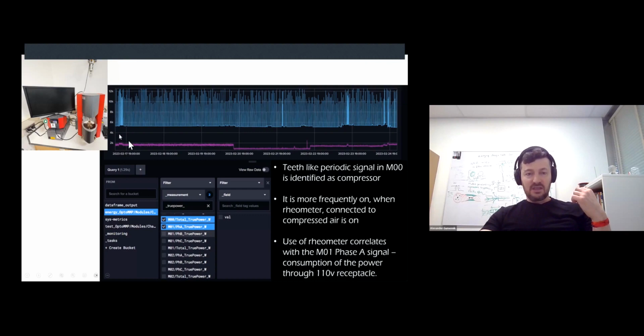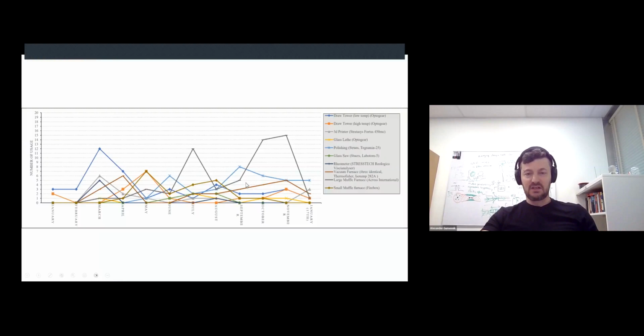We finally, after some investigation, found that on the signal that monitors inlets in this room, there is also a small rise that is correlated with the consumption of compressed air from the compressor. Knowing in which room the equipment is, we have been monitoring the use of equipment only in this room, and then we identify that it's related to the rheometer. So it's almost like an investigation every time you want to understand the signal.